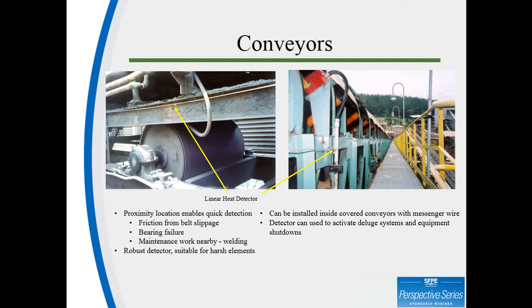This application is a perfect fit for our CTI Series linear heat detector because should there be any physical damage to the detector, it will not give you a false alarm. This assures that your deluge system or any other type of suppression system only activates on confirmed temperature initiation. Lastly, it's not uncommon for underground conveyors to be located in classified areas, Class 1, Division 1, or the ATEX equivalent. Remember that these classified areas can be protected with digital linear heat detection when employing an intrinsic safety barrier.